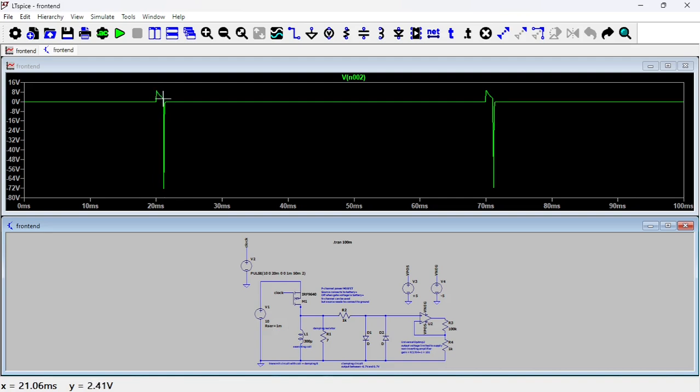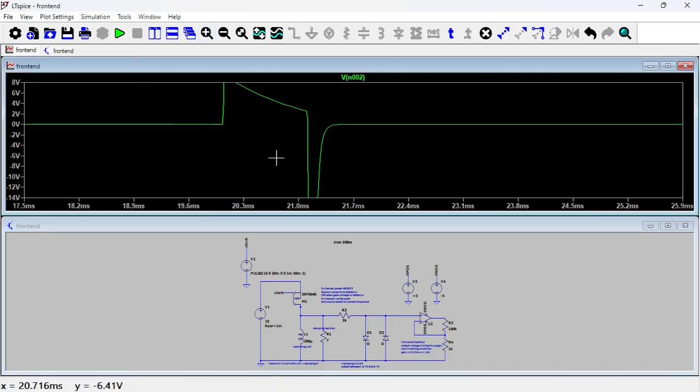And then what happens is that you switch off the coil and you get the flyback voltage. And that flyback voltage goes back to zero without oscillating. I mean, if you don't have the damping resistor, this thing is going to oscillate. So you put the damping resistor to go directly to zero, like this.